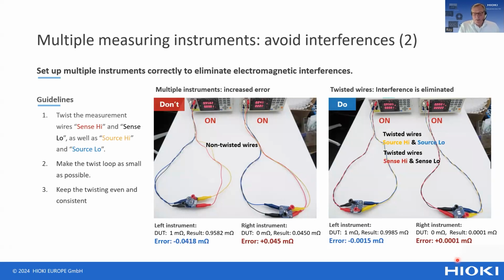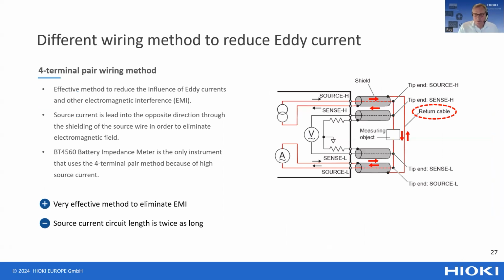By now you may conclude that twisting the wires solves all electrical interference and eddy current issues, but there is more to tell. Besides our standard battery tester in the BT3560A series, we have the BT4560 battery impedance meter that is also often used in the production line to measure the internal resistance at 1 kHz and also the electrode and reaction resistance of the battery at around 1 Hz. As the BT4560 uses a 1.5 A test current at its lowest range of 3 milliohm, it is important to eliminate the effect of electromagnetic induction and eddy current even more.